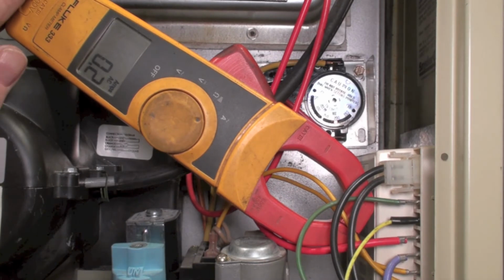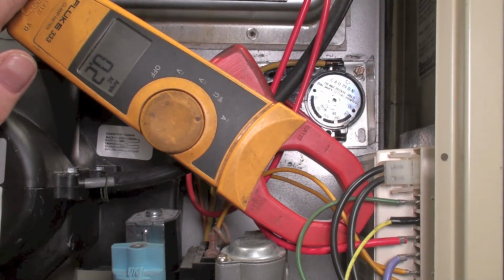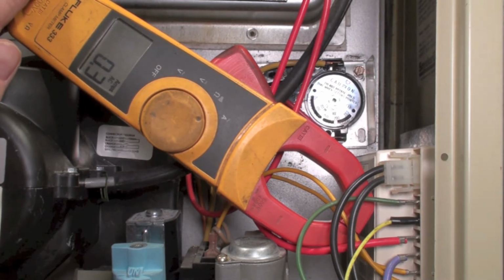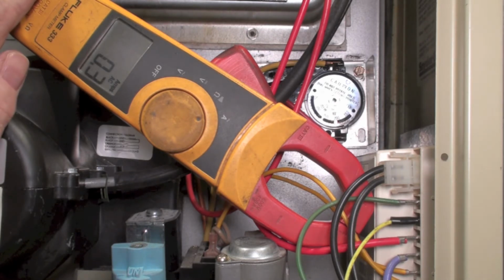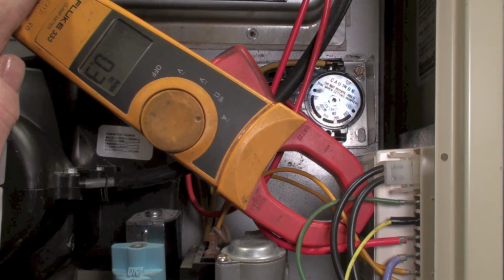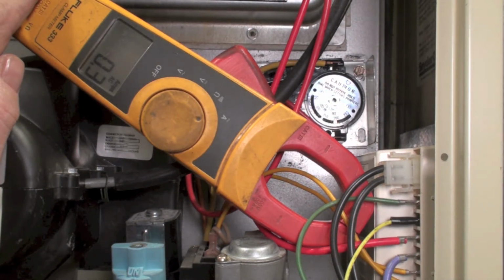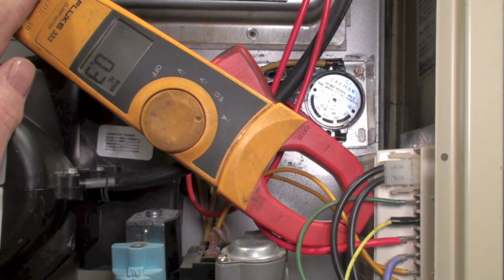Okay, what I've done here, this one's a little hard to tell whether it's burning or not. You can look through the inspection window, but there's an easier way if you just go ahead and clamp the gas valve. And you see I'm reading 0.3, 0.2 amps on this gas valve, so I know I'm burning. Now I'm going to be watching that limit switch back there and see if it'll go up and shut down. So what we're doing is we're testing to see if the fan motor has failed.